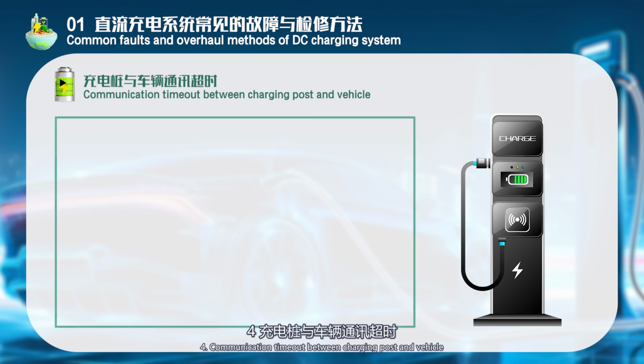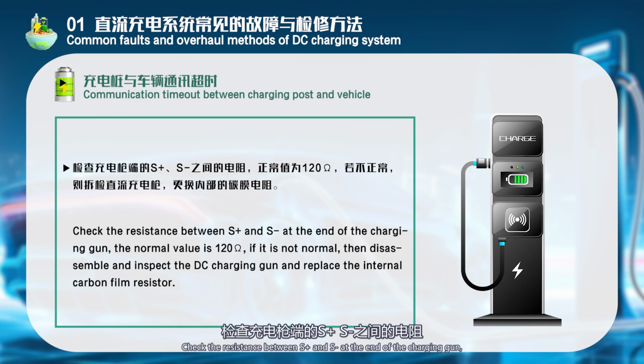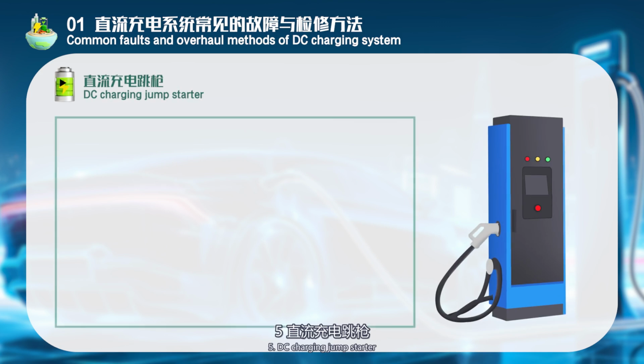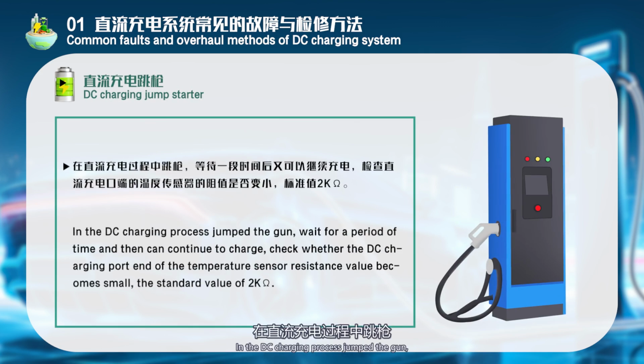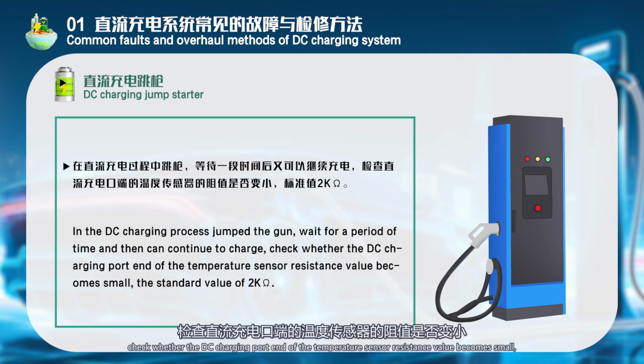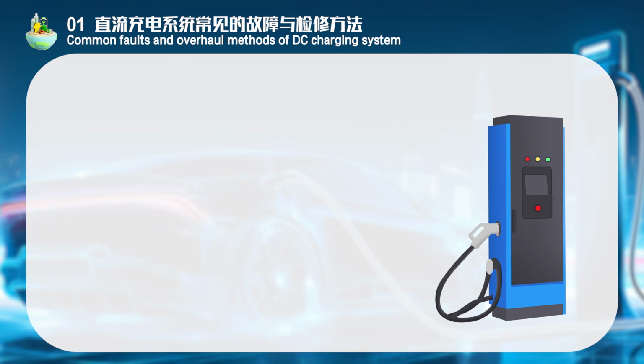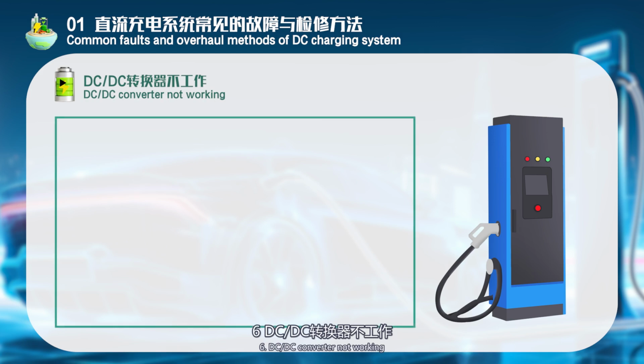4. Communication timeout between charging post and vehicle. Check the resistance between S+ and S- at the end of the charging gun. The normal value is 120 ohms. If it is not normal, then disassemble and inspect the DC charging gun and replace the internal carbon film resistor. 5. DC charging jump starter. In the DC charging process, jump the gun. Wait for a period of time and then can continue to charge. Check whether the DC charging port end of the temperature sensor resistance value becomes small, the standard value of 2 kΩ. 6. DC/DC converter not working.